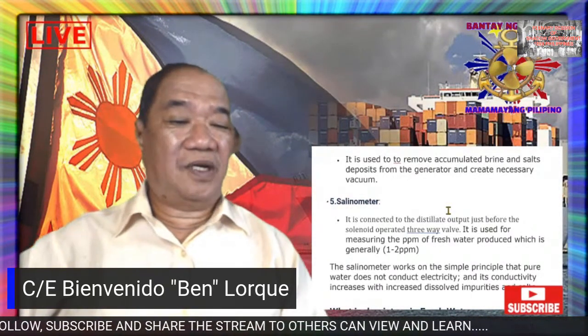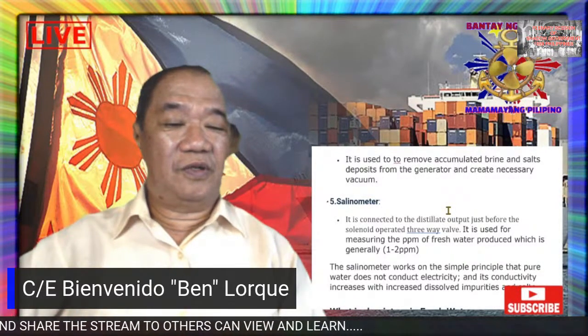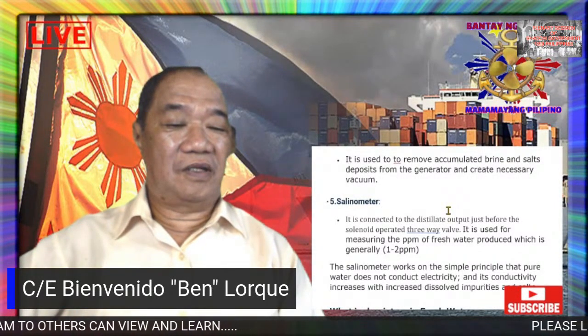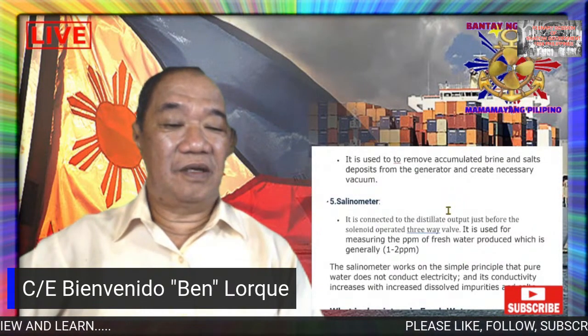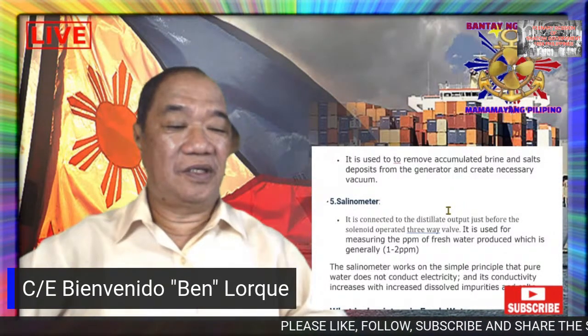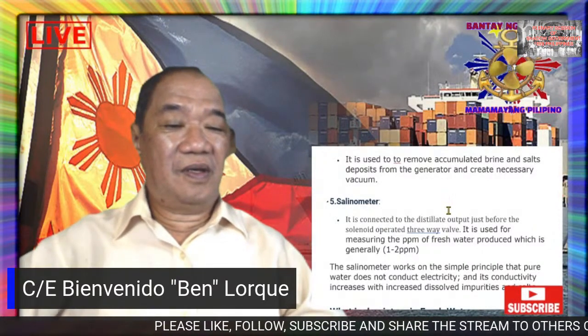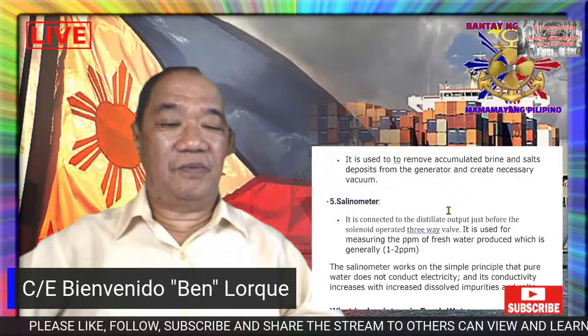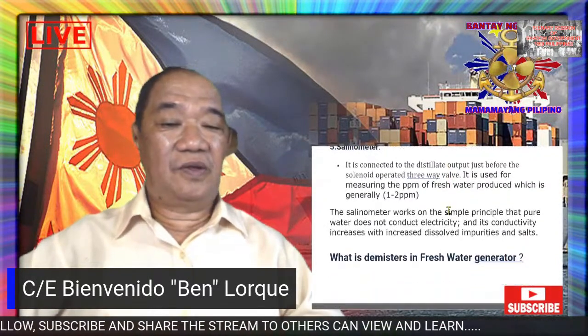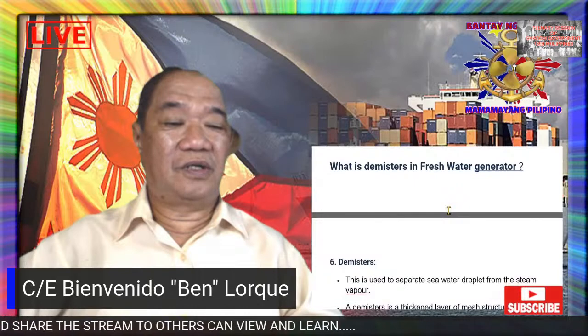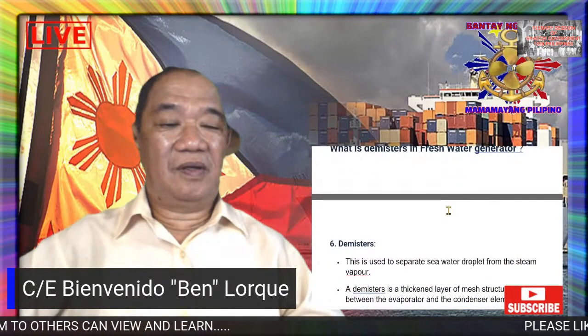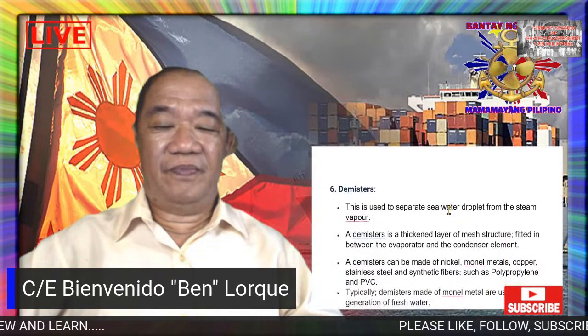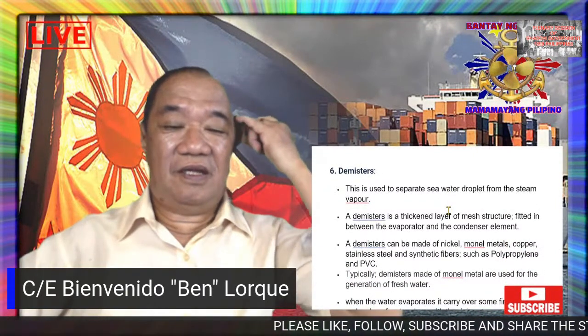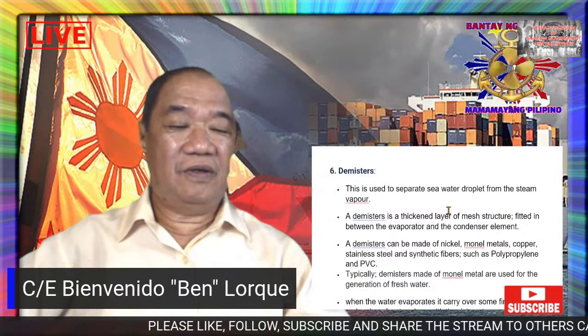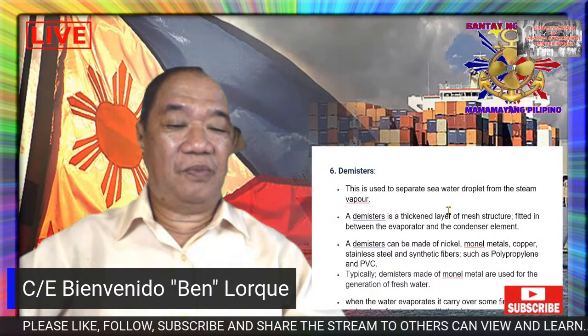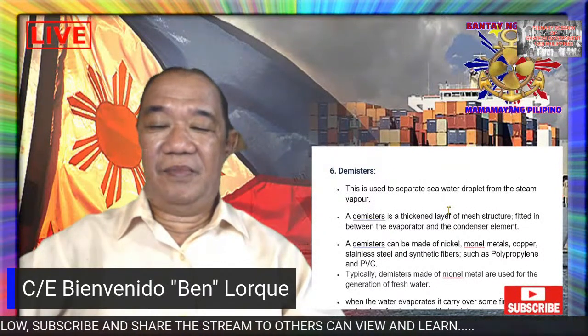Now, the salinometer works on the simple principle that pure water does not conduct electricity, and its conductivity increases with increased dissolved impurities and salt. Now, you will ask, what is demister in a freshwater generator? So, demister is used to separate seawater droplets from the steam vapor. A demister is a thickened layer of mesh structure fitted in between the evaporator and the condenser element.